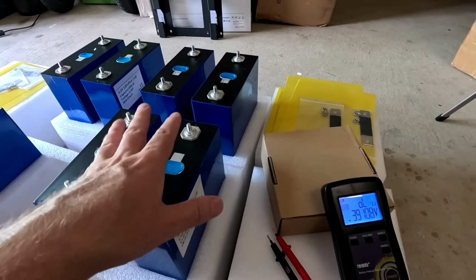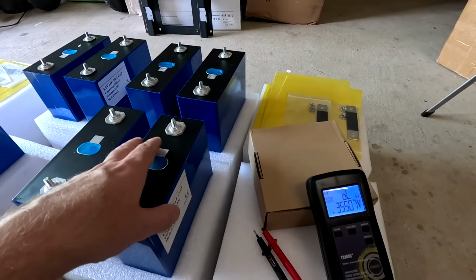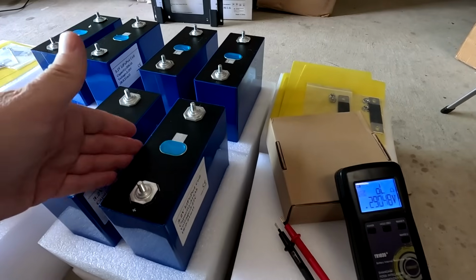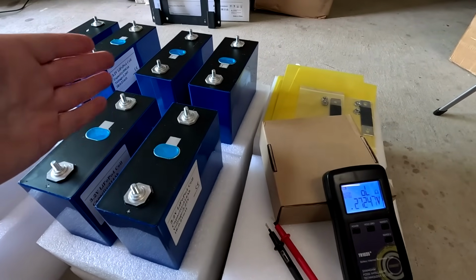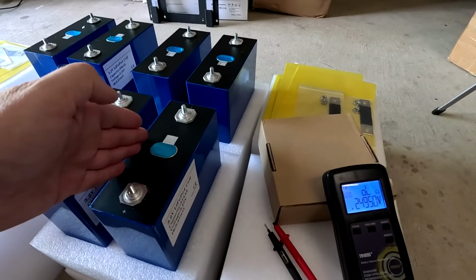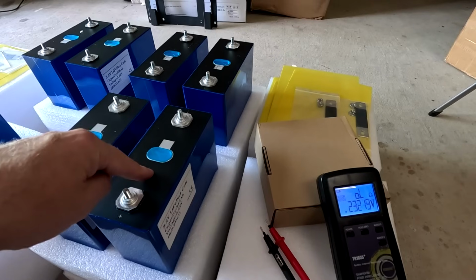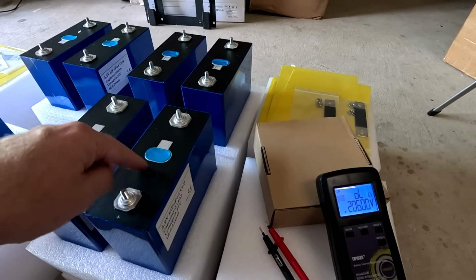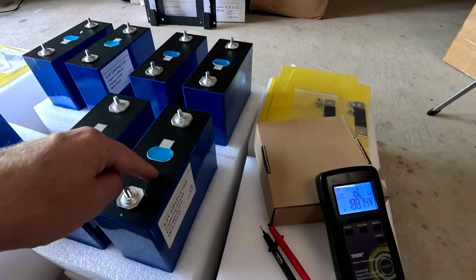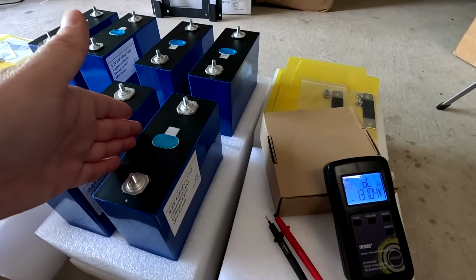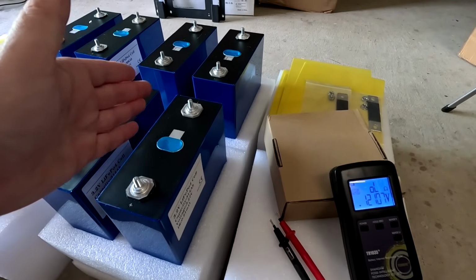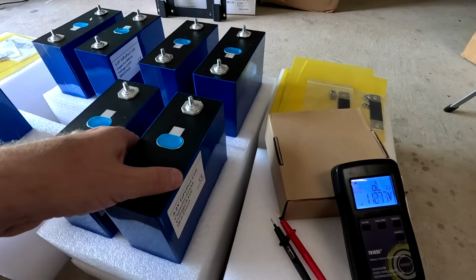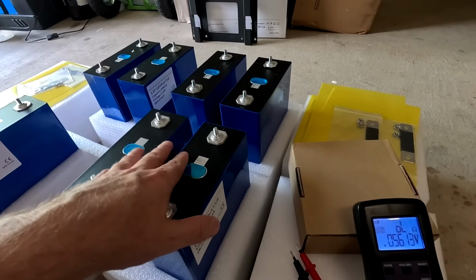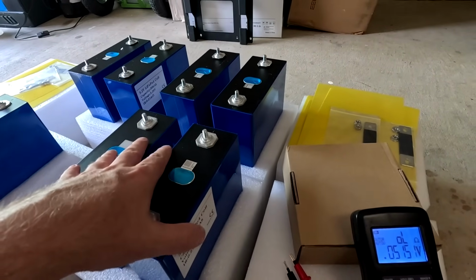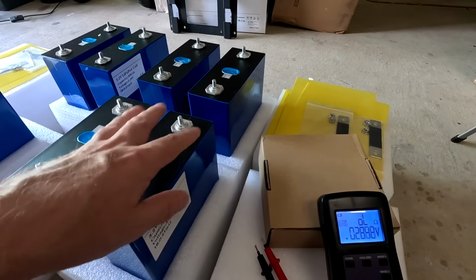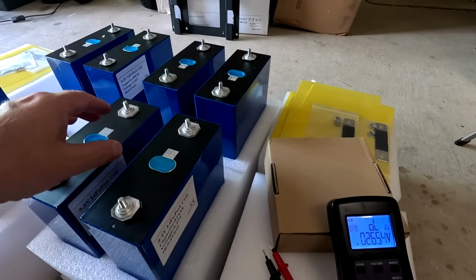Suppliers and manufacturers always say the batteries are voltage and capacity matched, but it doesn't really tell you anything about these batteries. This is a snapshot at the time of measurement. If one of the batteries would heat up, or I fully charge it and leave the others as they are, we'll have a different resistance. As time passes and the cells age, internal resistance will change as well. So it's really just a snapshot at the time of measurement, nothing else. I have stopped completely measuring these cells when I get them new.